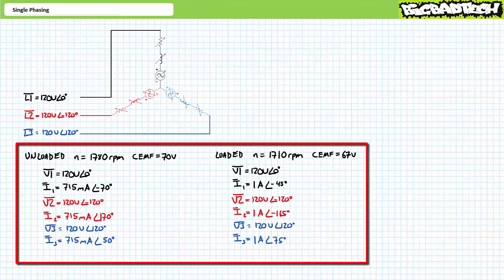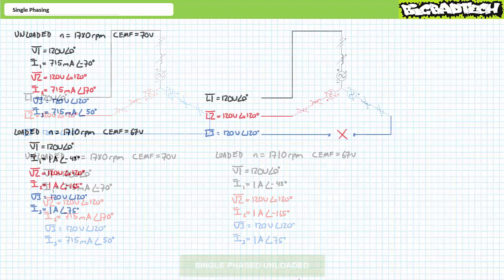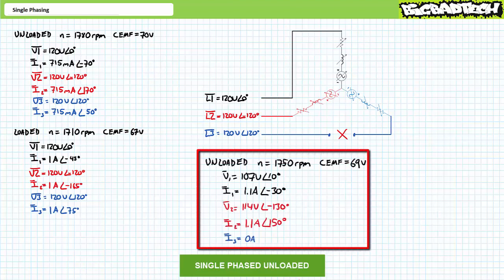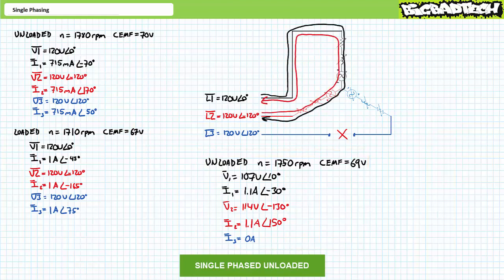Let's use those figures as the basis of comparison for single phasing events. Consider an unloaded Y-configured motor single phased while running by the unexpected loss of phase L3. The motor emits a growling sound and speed drops from 1780 rpm down to 1750 rpm. At that reduced speed, each winding now experiences only 69 volts of counter-electromotive force. Current in line 3 — the lost phase — is zero amps. Two branches of the Y configuration remain connected, with a single path for current through the series combination of windings one and two. Although you'd think they'd divide the line-to-line differential evenly, while the unbalanced motor is still running, they don't.